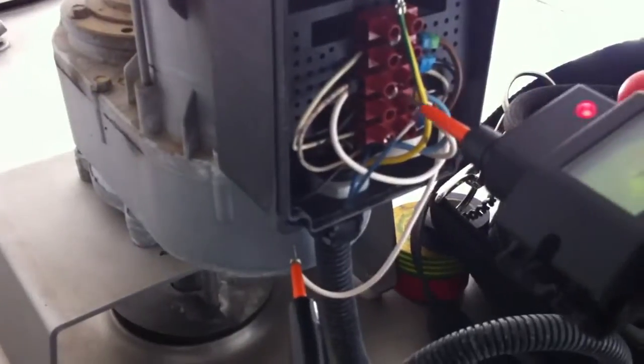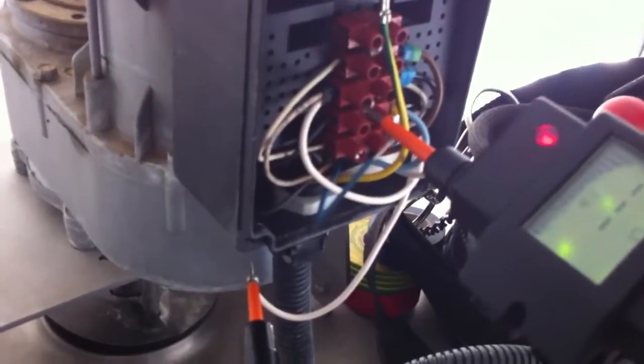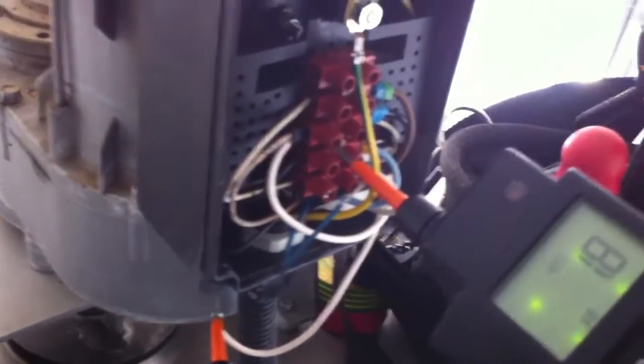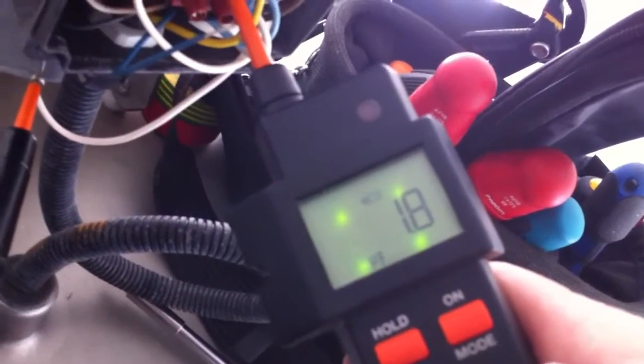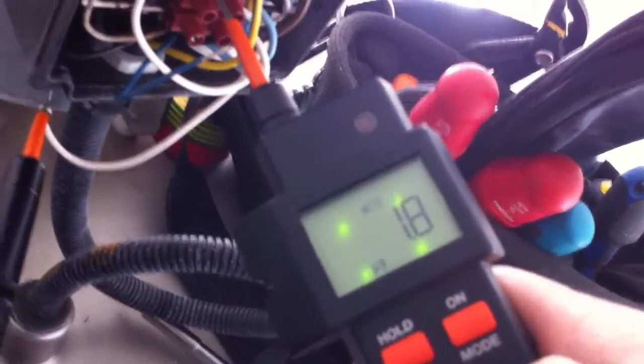This is the good one, the one that was running. That measures 1.8 microfarads. Should be 4. So I'm going to get a new one put on there.